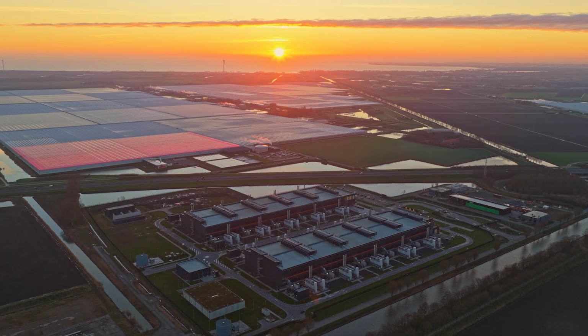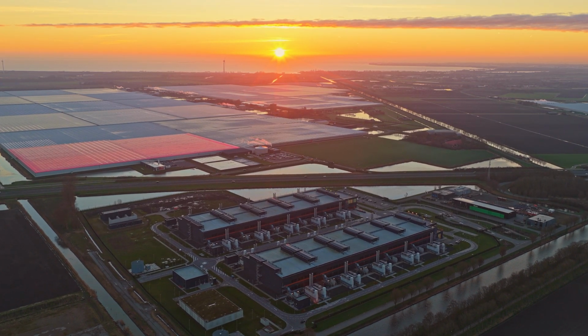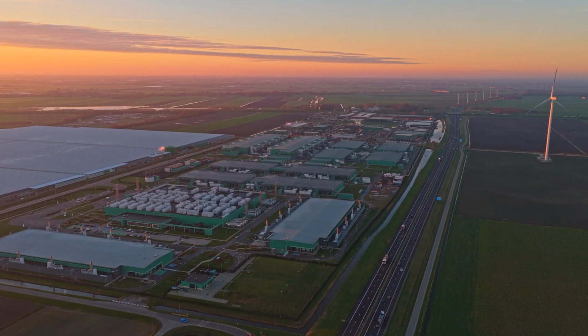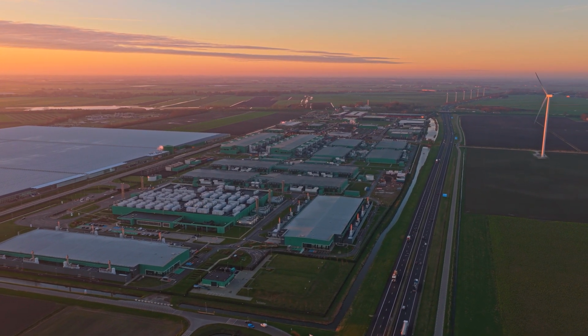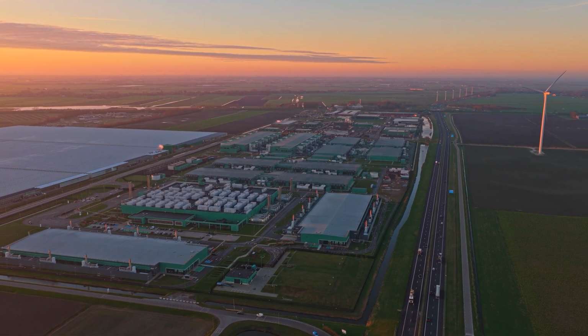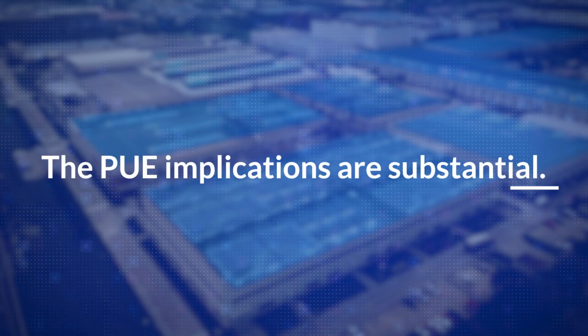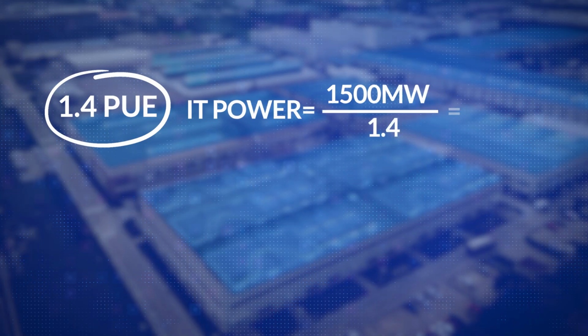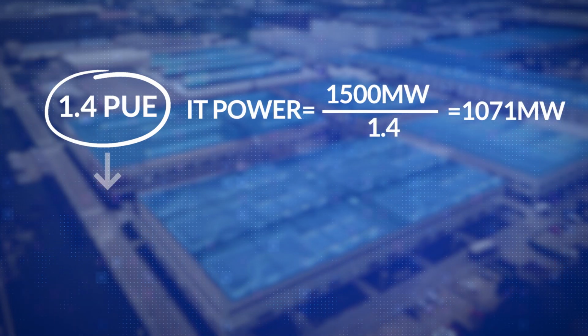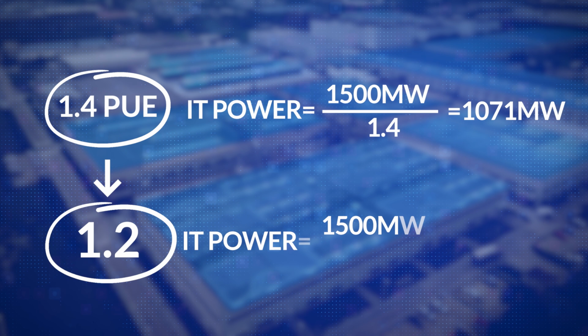What if adiabatic cooling, integrated system design, and a new approach to plant architecture could significantly reduce the energy required to support the next generation of high heat density computing? The PUE implications are substantial. Most facilities today operate in the 1.4 to 1.5 PUE range. This innovative approach moves closer to 1.2.